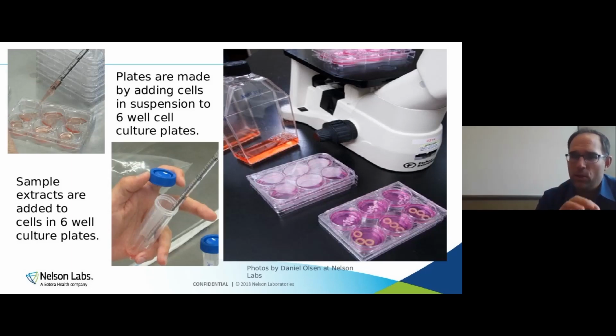And then we take that solution and we put it onto the test, in this case, the cells. So these cells then respond to whatever toxins could be in the masks. So that's the cytotoxicity test. It's very sensitive. And when we've done inside investigations within Nelson, we did a 10-year investigation where if a device failed a test for biocompatibility, 93% of the time, it was the cytotoxicity test.